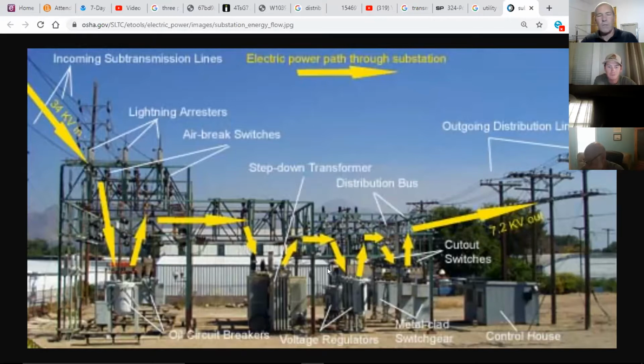So configuration wise, as far as drawing is concerned, that just goes back to show you, I don't need neutral, excuse me, you do need ground. I don't need neutral on my transmission system, because where is it going to? A substation. And from that point on, do I now need a neutral out of the substation? That's where you're going to need it. Also, and we're going to talk economics again, if I don't need a neutral on transmission, I don't need to pull one. That's an extra conductor I don't need.